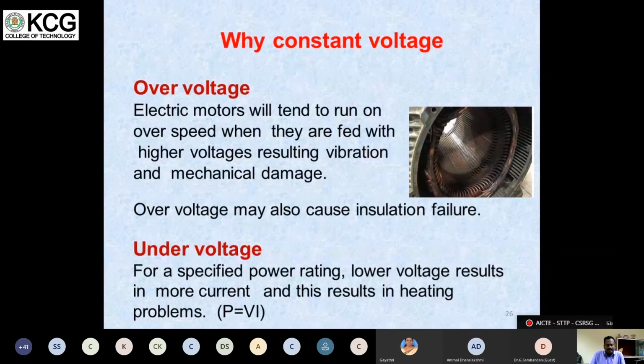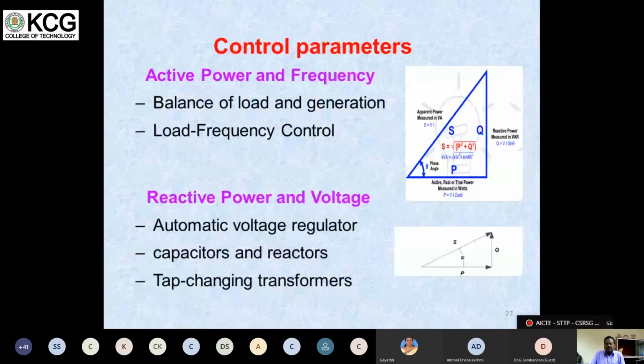Over frequency and under frequency are also not desirable in the system. So all we are aiming for is keeping voltage and frequency constant. Now we discussed what the problem is with higher voltage, lower voltage, higher frequency, lower frequency. Now, how to control this voltage and frequency? There are some control parameters, control mechanisms to control voltage and frequency. As you know already, at the generator we generate active power and reactive power. Active power and reactive power.